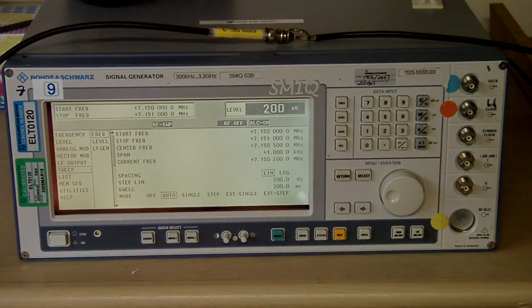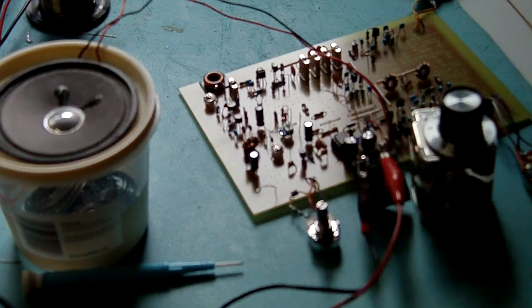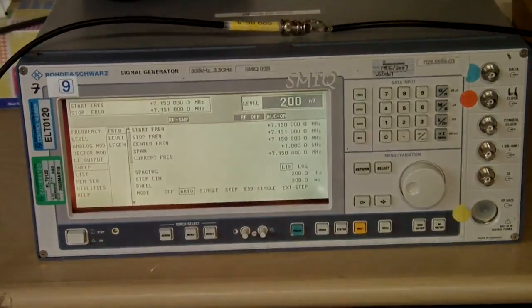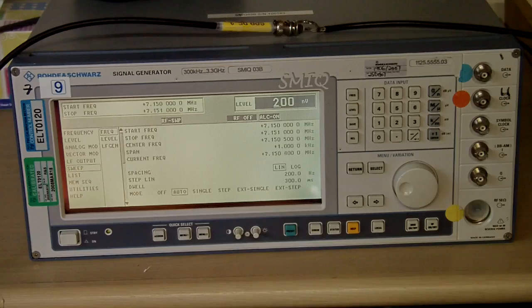RF is off now. I'll turn on the receiver. I will apply an RF level of 200 nanoV, which is the equivalent of minus 121 dBm, turning RF on.